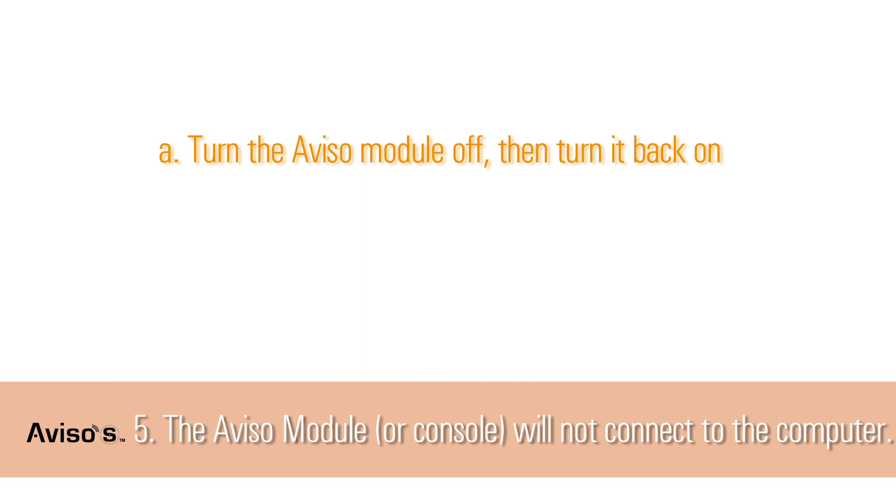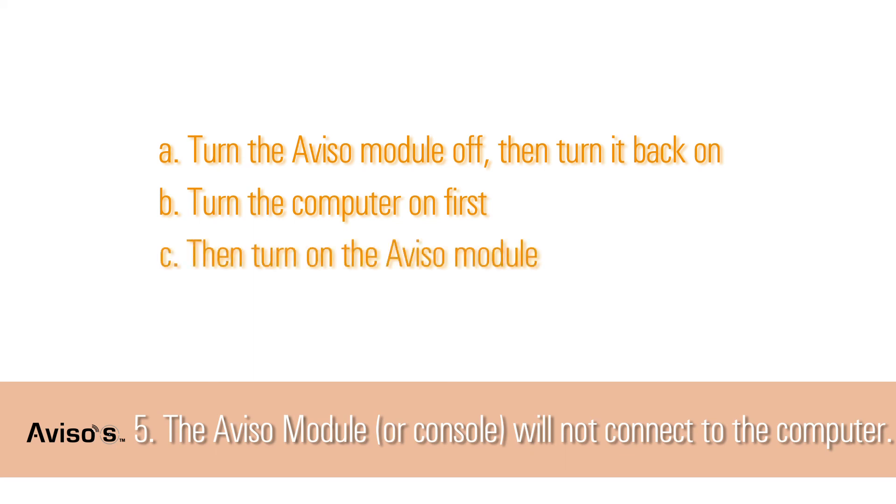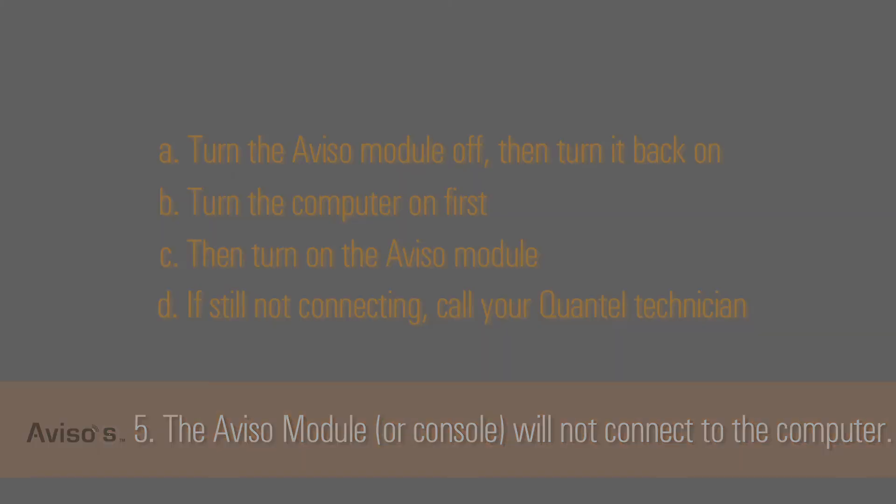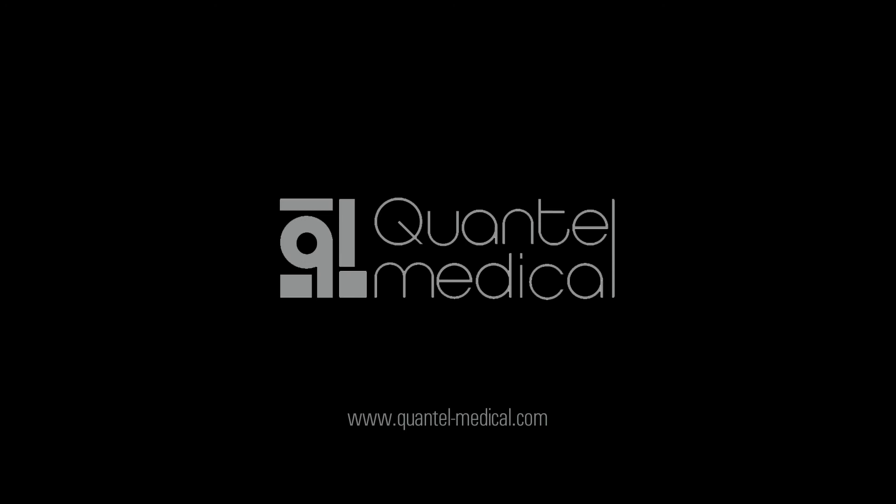Turn the Aviso module off, then turn it back on. Turn the computer on first, allowing the software to start up. This can take a while. Then, turn on the Aviso module. If this does not help, the drivers must be reset. A Quantel technician is required for this. Quantel Medical's exemplary ultrasound technology has brought multiple innovations to ultrasound specialists worldwide since 1993. We hope you've found this demonstration of the Aviso-S helpful. For more information about this technology and Quantel's complete range of diagnostic ultrasound products, please visit www.quantel-medical.com.